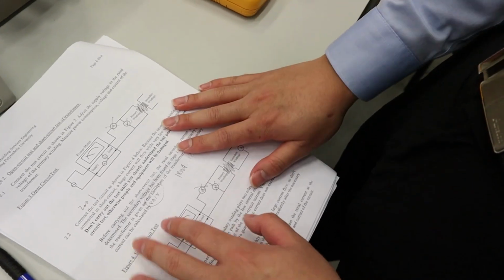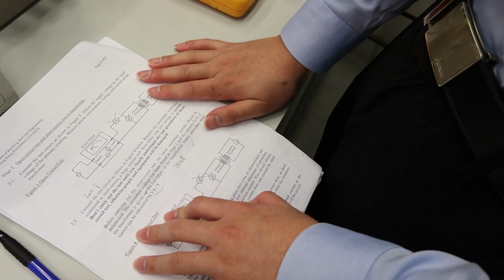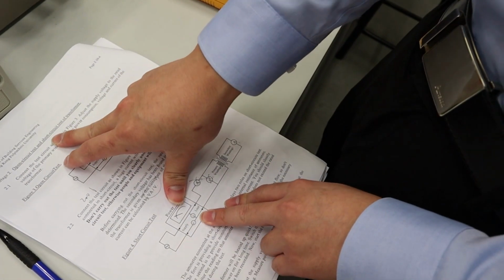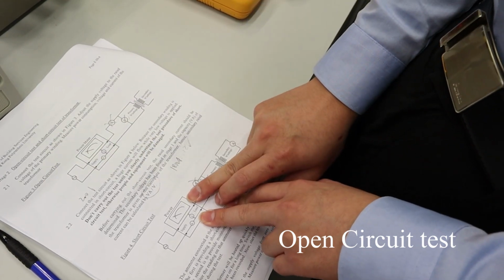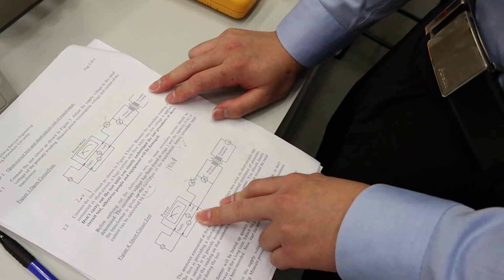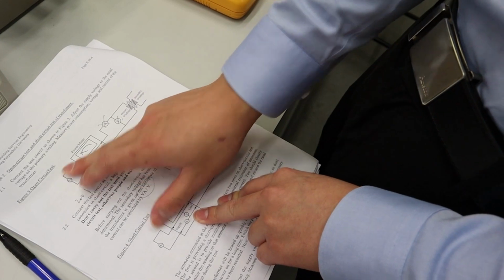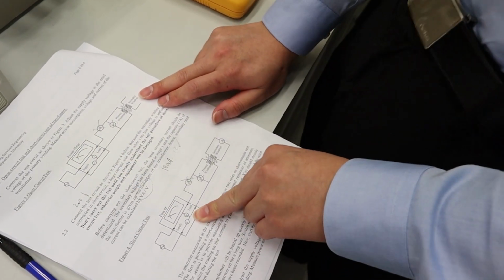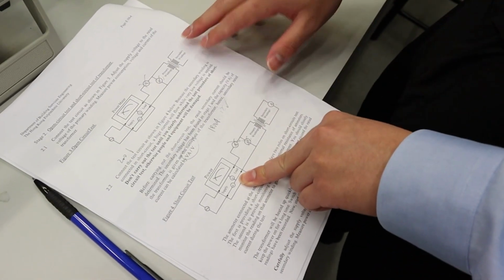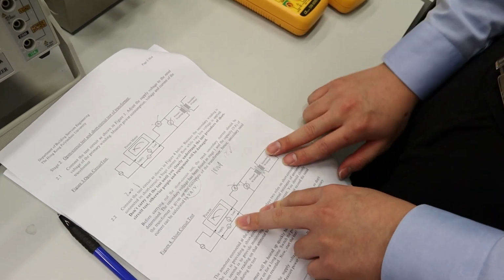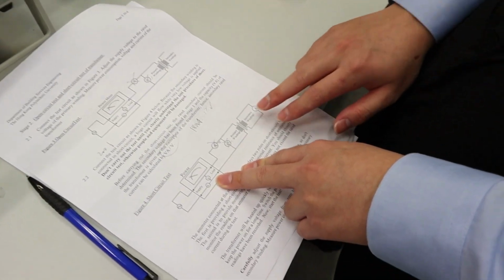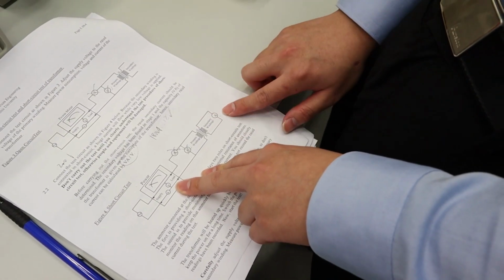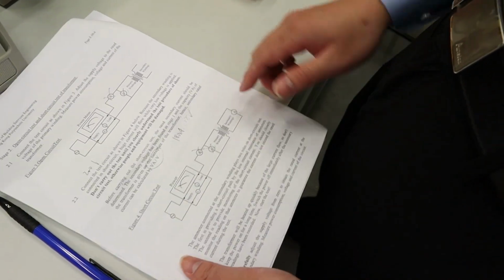So let's start the second experiment, about the open circuit test. The difference between the open circuit test and the short circuit test is on the secondary windings. In the open circuit test, the secondary winding is an open circuit, not connected to anything. But in the short circuit test, the secondary winding is connected to a current meter.